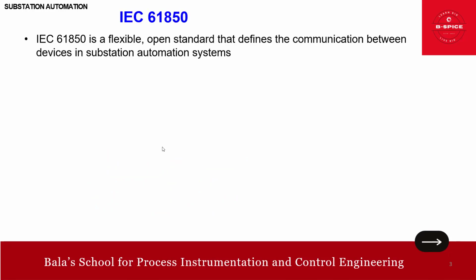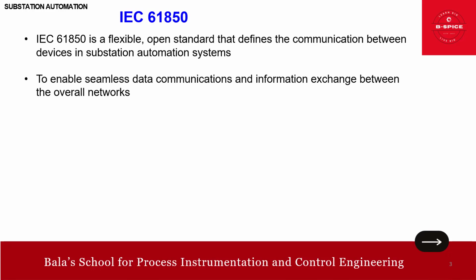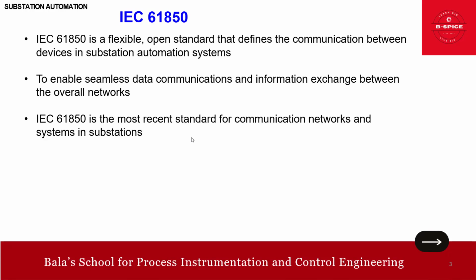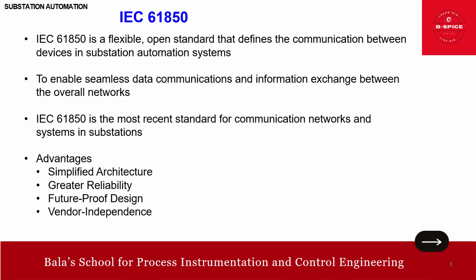IEC 61850. Just our intro again: it's a flexible and open standard that defines the communication between devices in a substation automation system, enabling seamless data communication and information exchange across the overall network. IEC 61850 is the most recent standard for communication networks and systems in substations. Its advantages include being very simplified, greater reliability, future-proof design, and vendor independence.